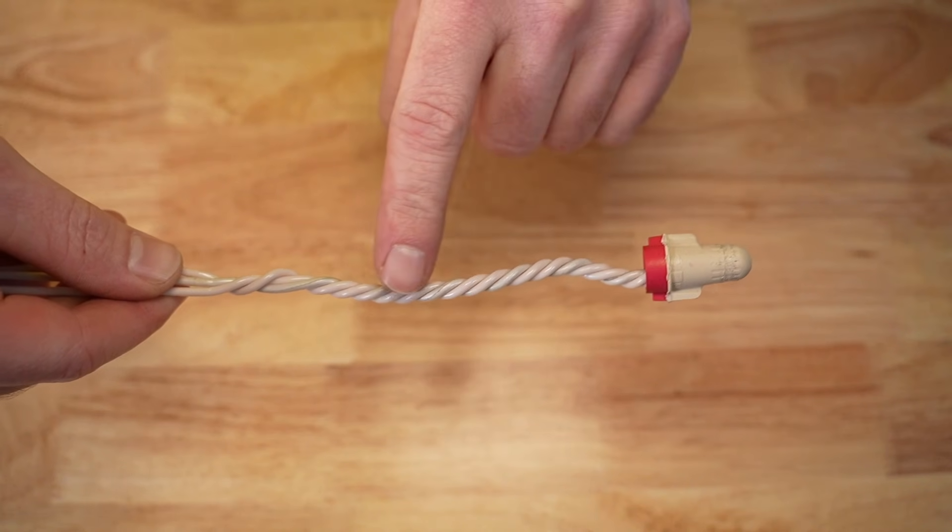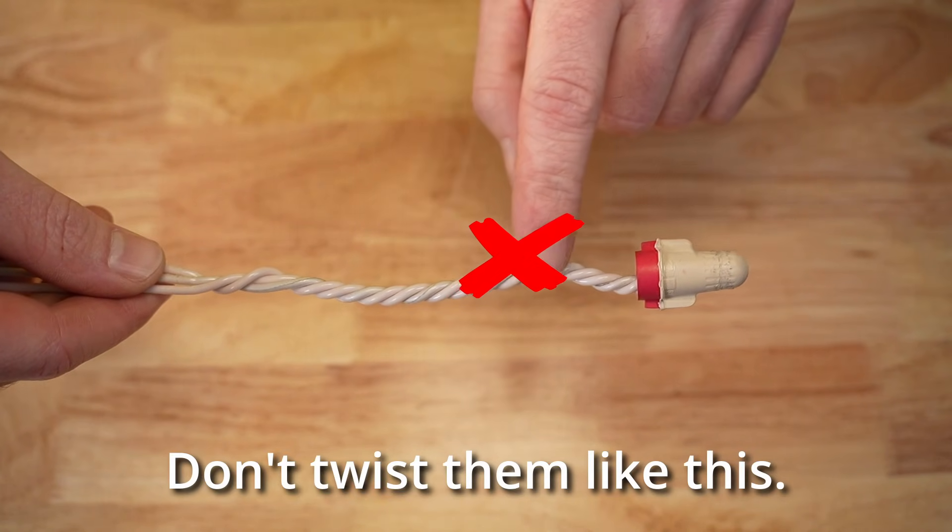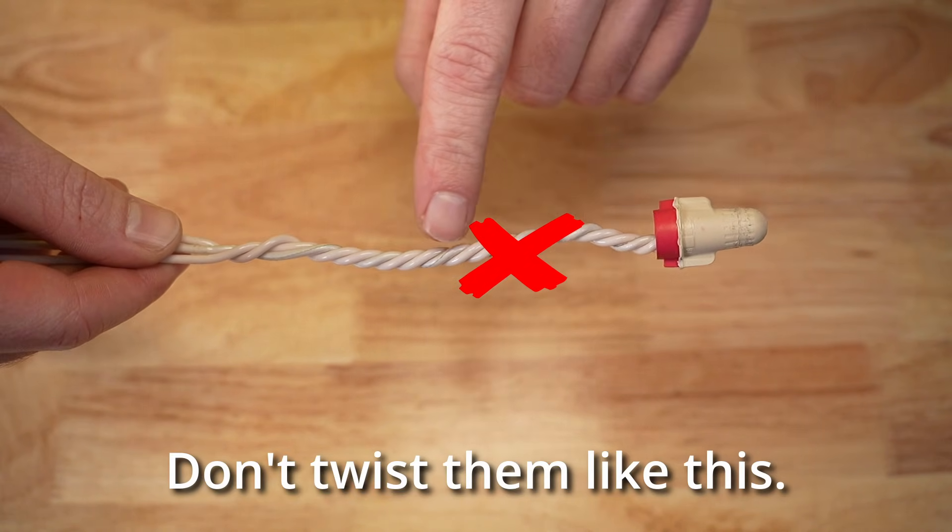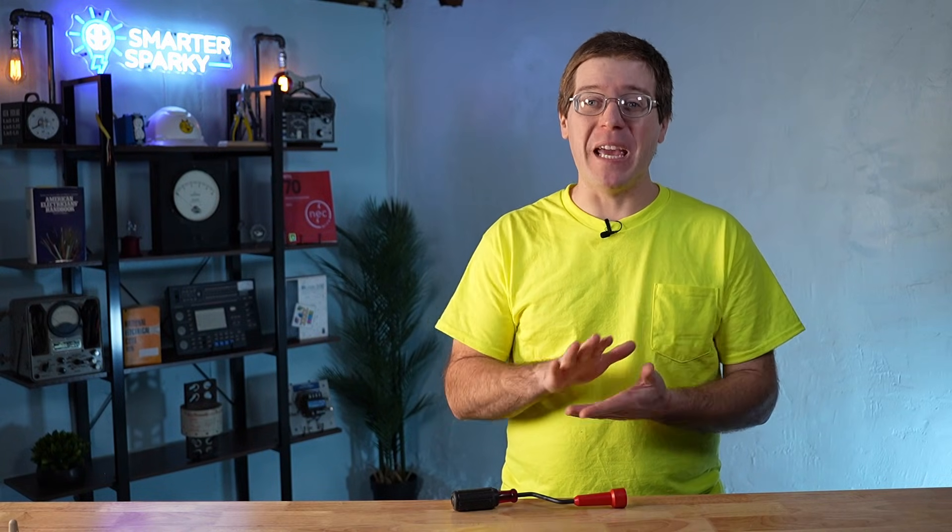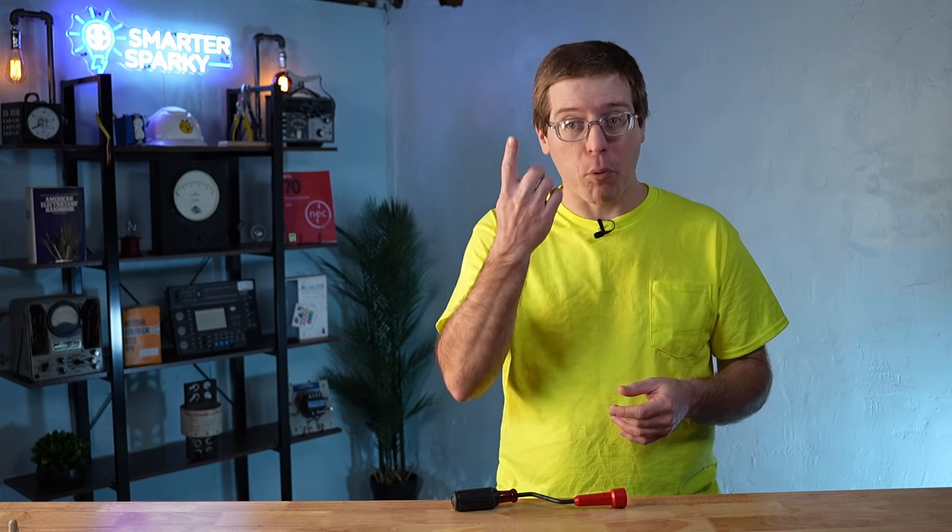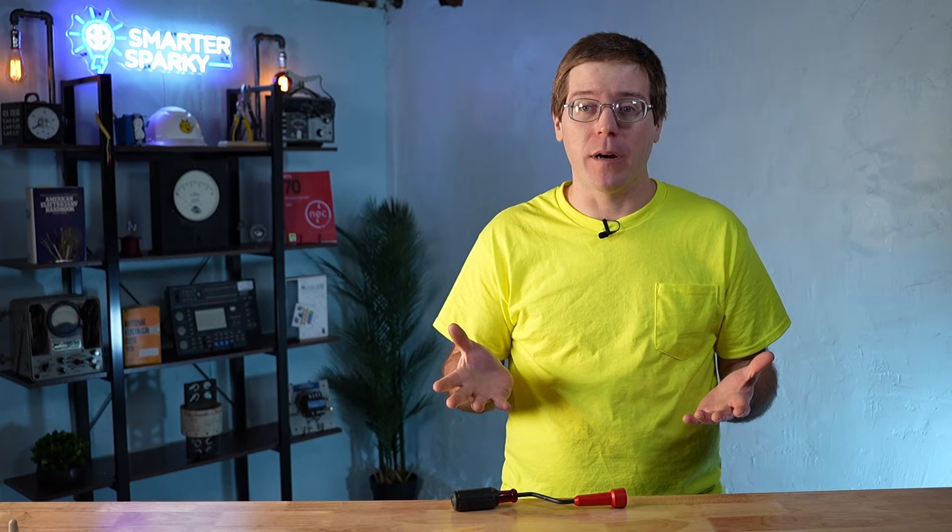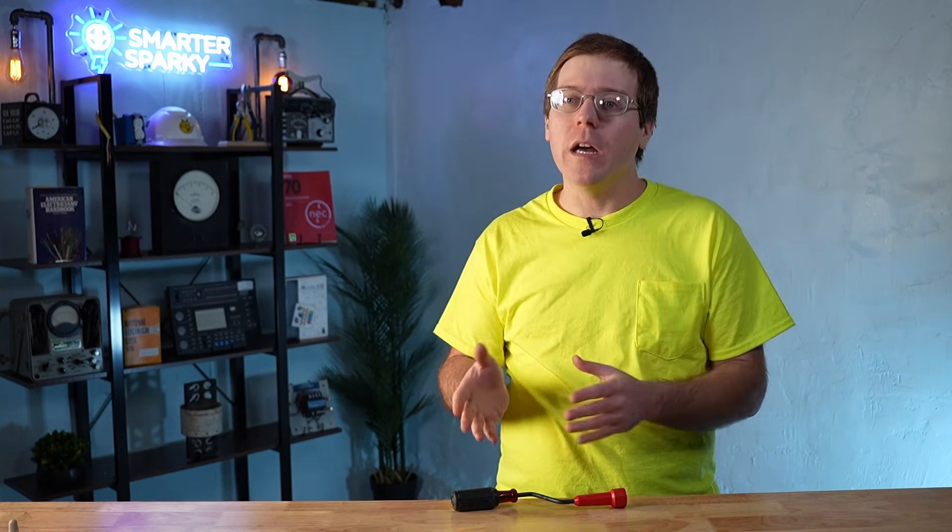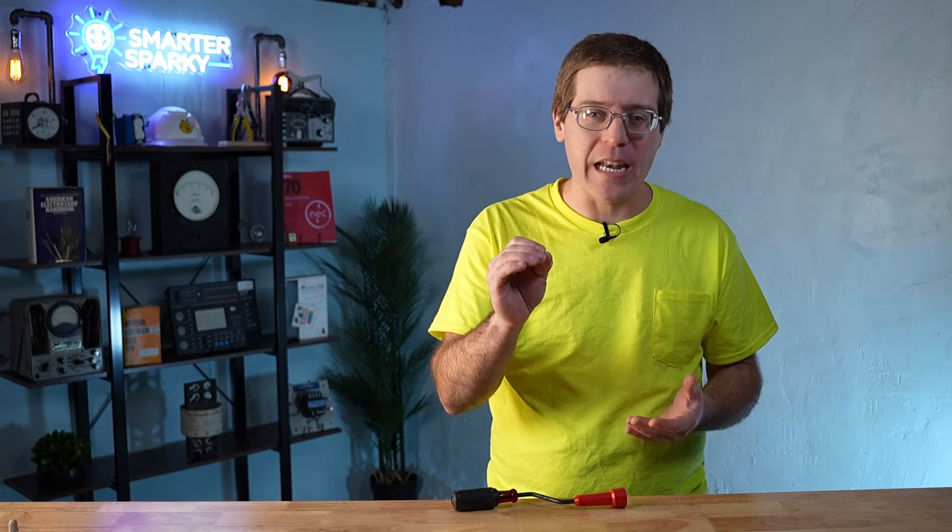However, when used incorrectly, they can easily over twist a splice, which creates problems down the road. Over twisting can make future troubleshooting and maintenance a headache. And in some extreme cases, it can actually cause the conductor to break through the top of the wire nut, potentially exposing live copper. No matter how you install a wire nut, by hand or with a tool, the goal is a secure connection, not maximum torque.